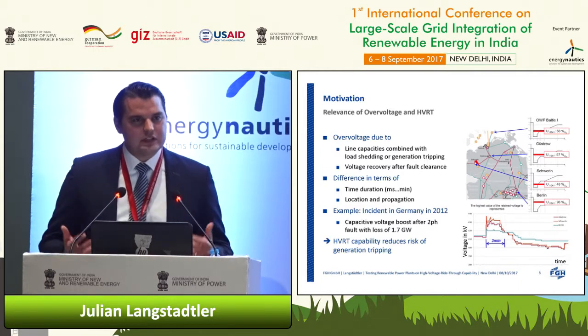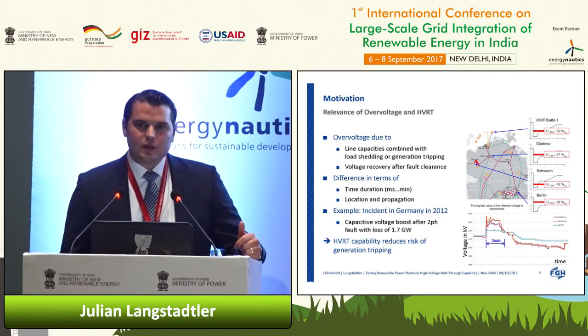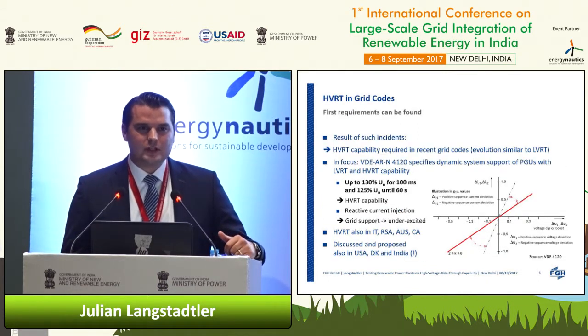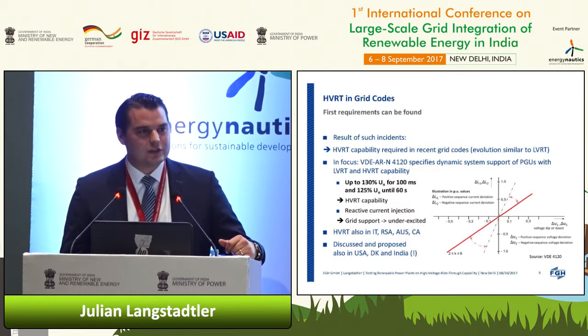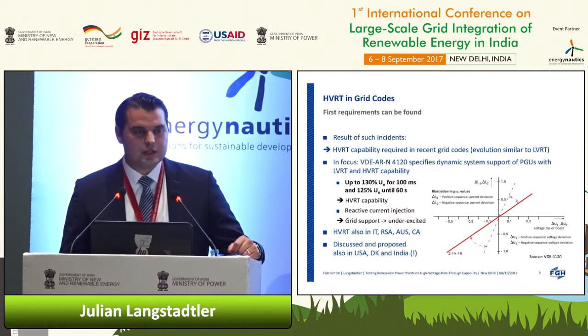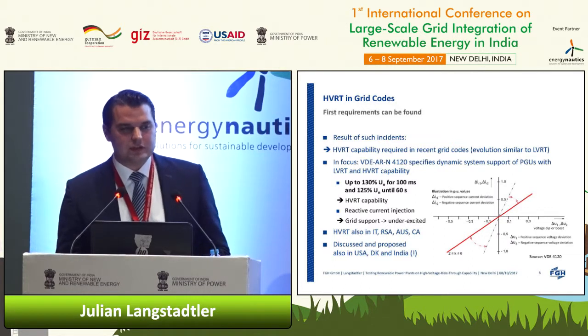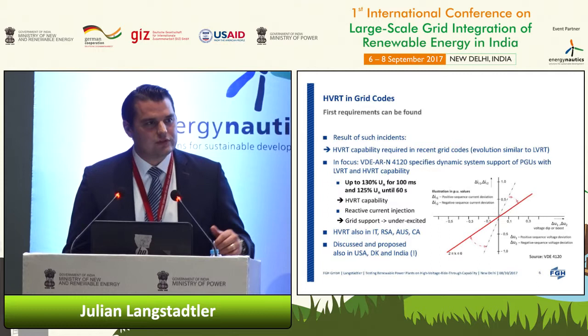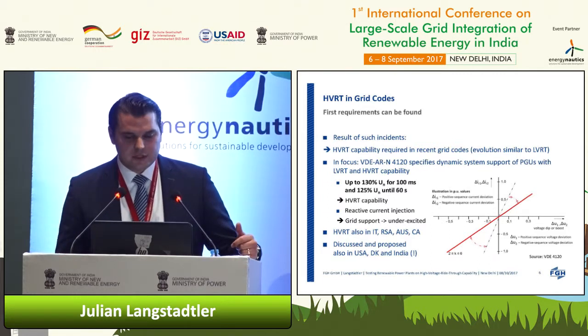So whenever such an incident occurs, you will try to avoid that it will ever occur again. So the result of such incidents is always that there is afterwards a requirement found in the grid code, and it is highly discussed, of course. So actually the result is that there's an HVRT requirement, and the capability is required in the recent grid codes. And we expect that there's also a similar evolution for HVRT requirements that we've seen for LVRT.